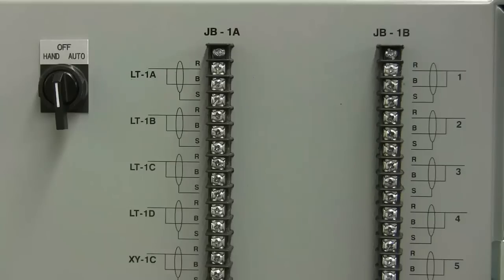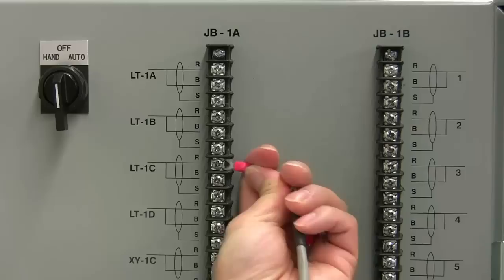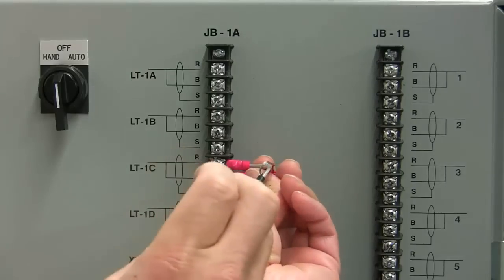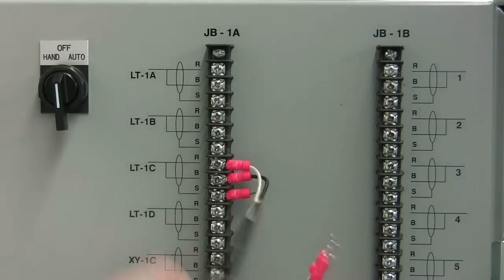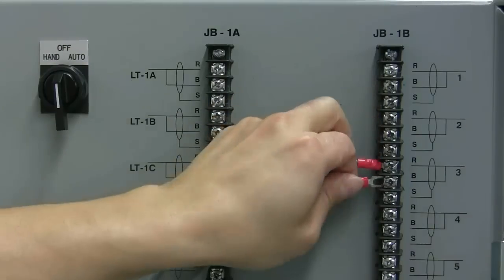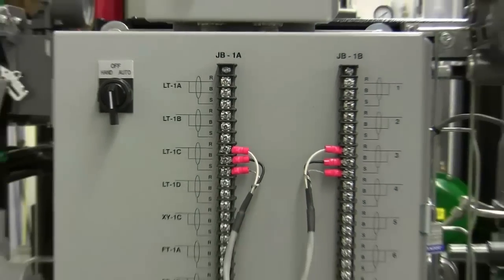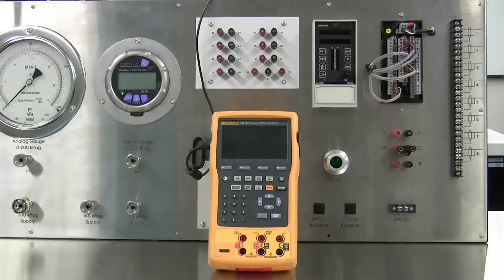To connect the transmitter to the power supply, we need to bring the transmitter from the field to the control room side. To do this, connect LT-1C to one of the conductor pairs on JB-1B. The level transmitter is now connected to TS-1 on cable pair 3.